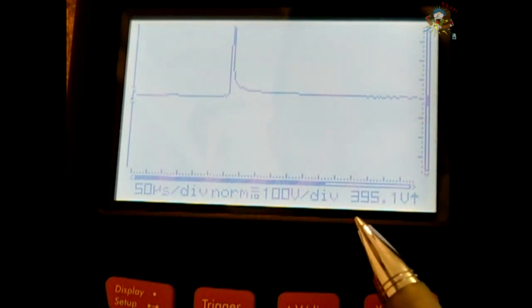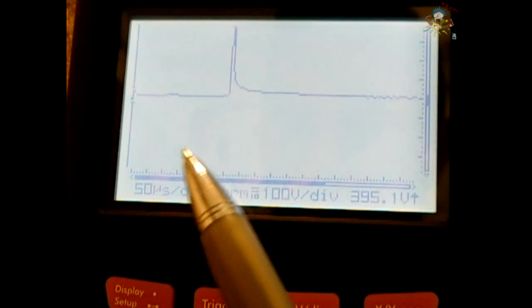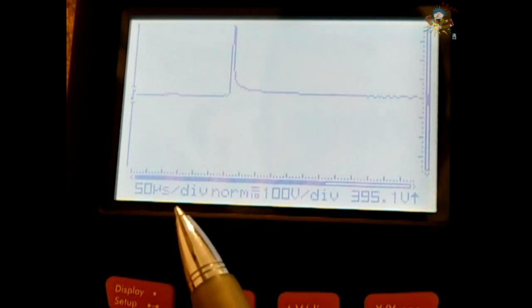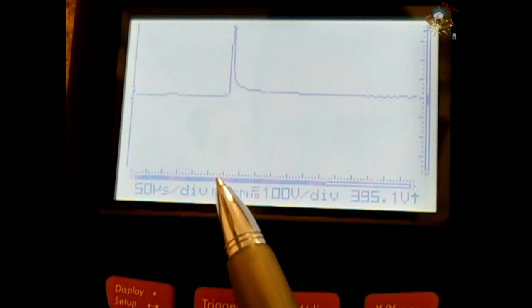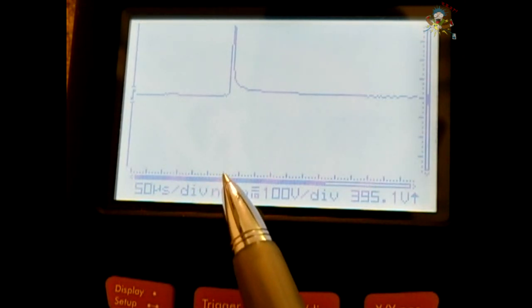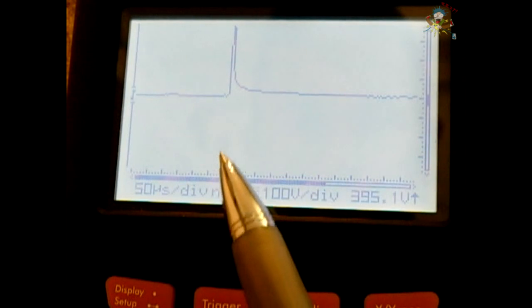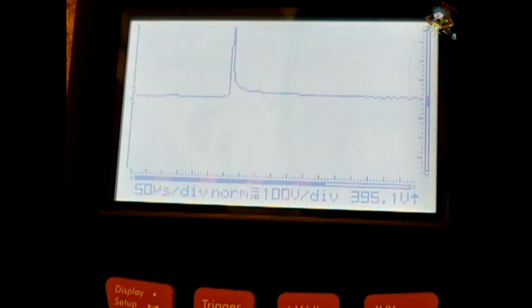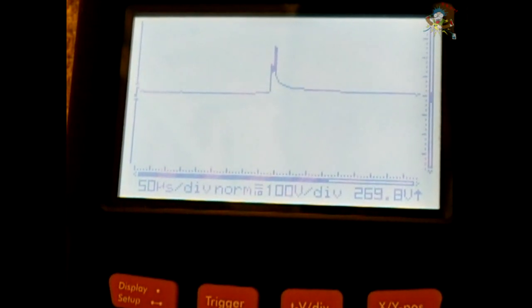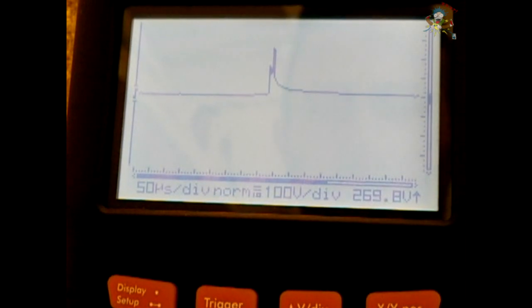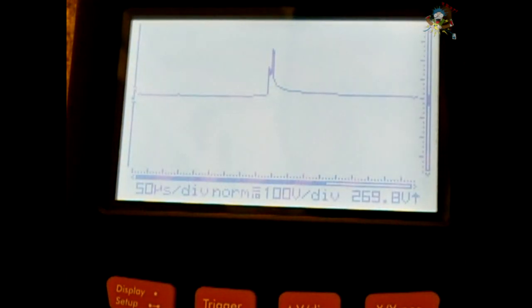The reason why you're not seeing it show up here now, each one of these 100 volts so up 100, 200, 300, this is just over 400 volts when I release power from that relay coil. I'm going to do now, let's do it again. I'll click on and off, I'll put power on and you can see right here that created a 395 volt spike right there shooting up.